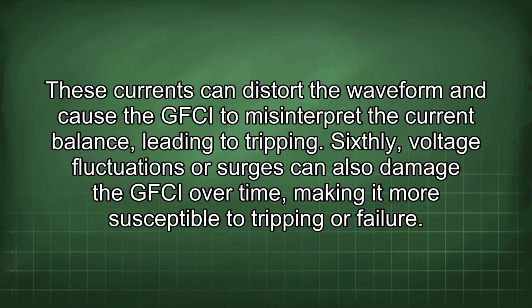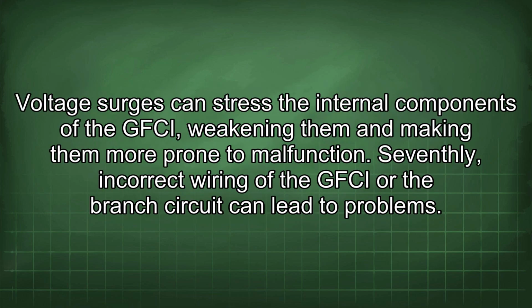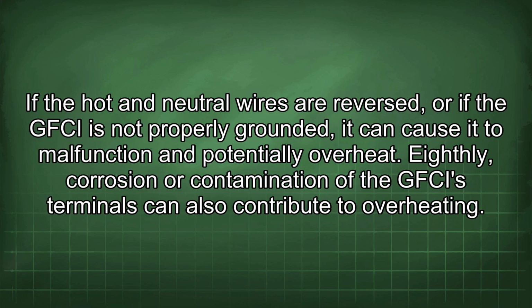Sixthly, voltage fluctuations or surges can also damage the GFCI over time, making it more susceptible to tripping or failure. Voltage surges can stress the internal components of the GFCI, weakening them and making them more prone to malfunction. Seventhly, incorrect wiring of the GFCI or the branch circuit can lead to problems. If the hot and neutral wires are reversed, or if the GFCI is not properly grounded, it can cause it to malfunction and potentially overheat.